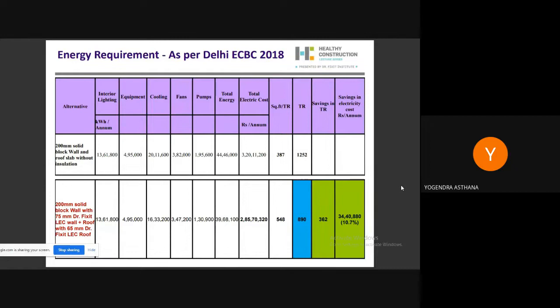So the total energy requirement is coming out to be 39,68,100, and the electric energy cost will be 2,85,70,320. And if we check the square feet per ton rating, it will cover 548 square feet per ton. So the ton rating demand will be 890, as against a 1252 ton rating demand for cooling this building in non-insulated structures. So the saving in ton rating is 362, and the saving in electrical consumption is 34,40,000 per annum.